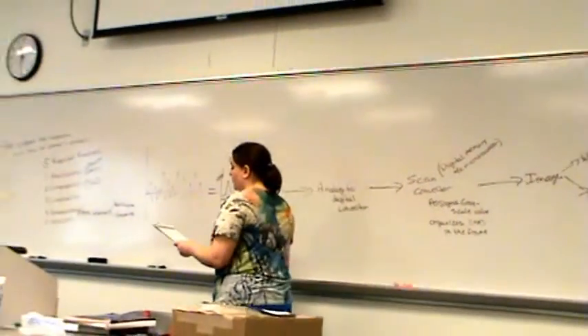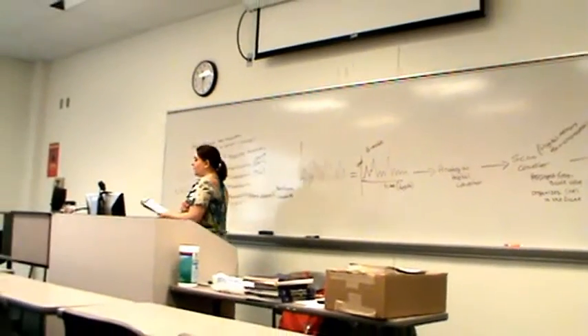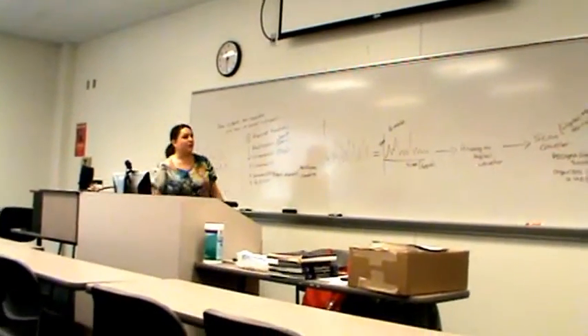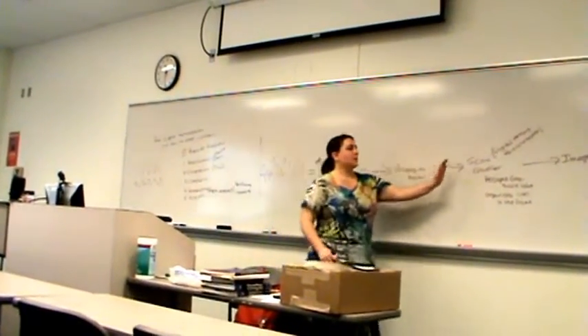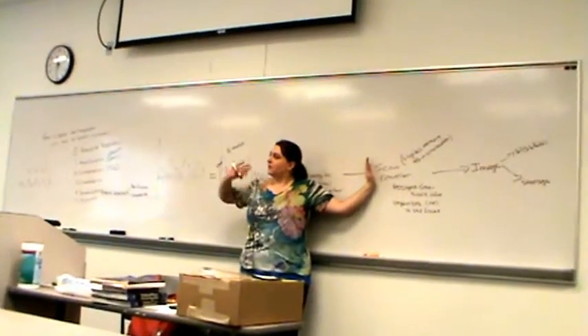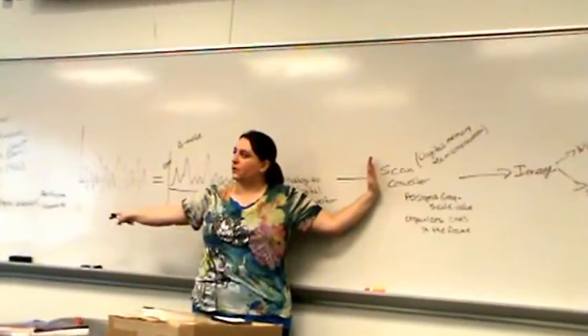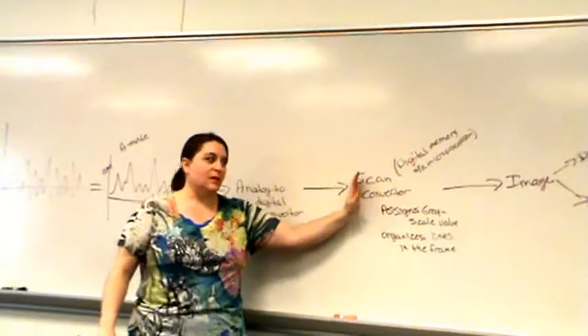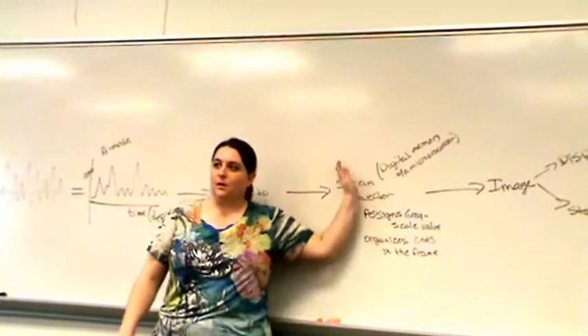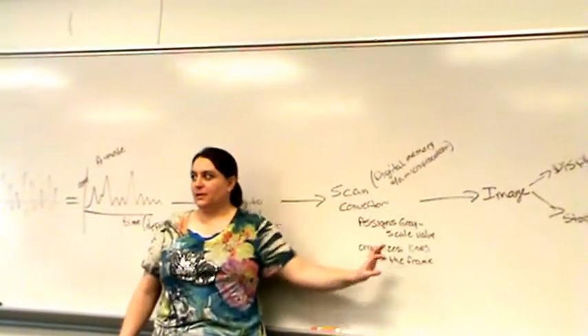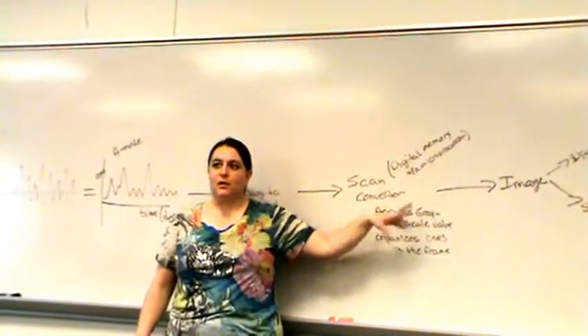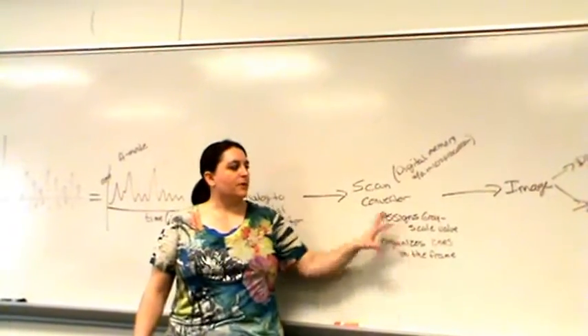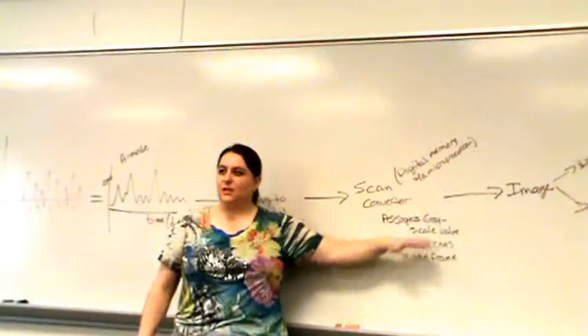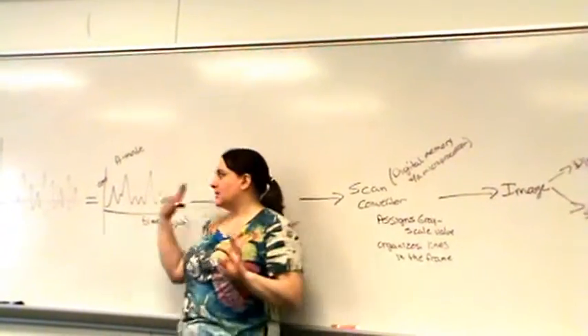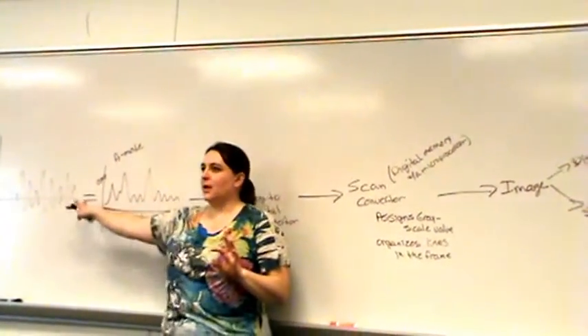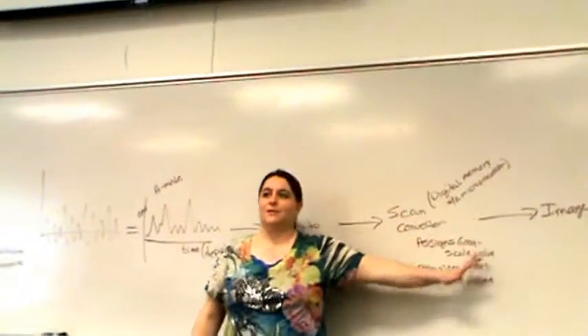Remember there's that whole idea of pre-processing and post-processing. Pre-processing is anything that can affect the signal before it gets here. Pre-processing is all of this stuff that happens before we get to scan conversion. Post-processing is something that we can do to this signal once it's been stored. So post-processing typically is things like measurements, calculations. There's a few other things that we can do once it gets to this point. But pre-processing traditionally is anything leading up to the scan converter, and post-processing is anything past the scan converter.